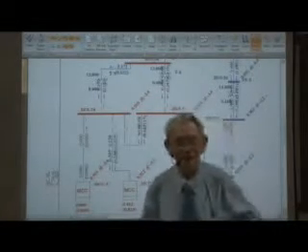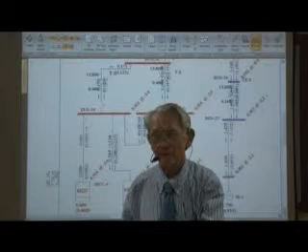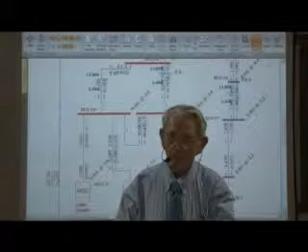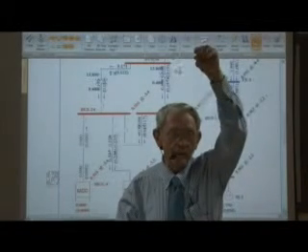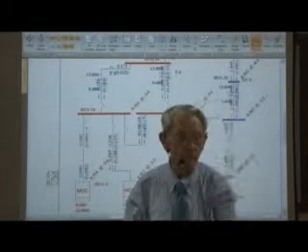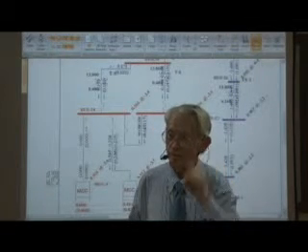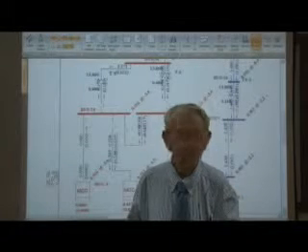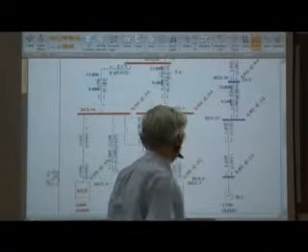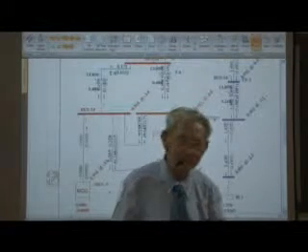Well, the wires are still going. You know, the wire came from the top, went through some transformers and buses, and down to the bottom. And when I turned off the power, of course the power didn't go. Then I made this tie breaker, and the wires are still there, and I re-energized the bus from the bottom, from the other side, from the low voltage side. It doesn't matter where I energize it from. I cannot put my finger in that bus if I want to live a long time. So you look at it and say, well, thank God for a computer program, because I might have done that. That's bad. That isn't going to work.